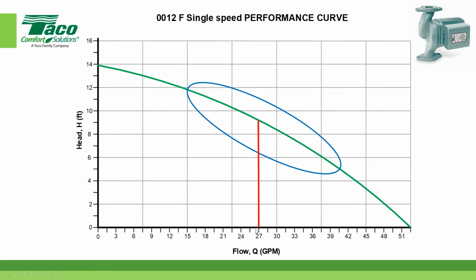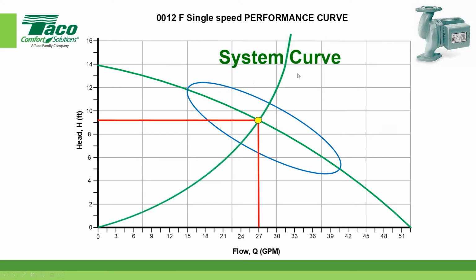The actual best efficiency point is right smack in the middle of that filet, or generally speaking, right in the middle of the circulator performance curve. So in this case, this would have the ability to do 27 gallons a minute at about 9 foot of head, and that would be its BEP, or best efficiency point. In this case, if that's where I was running, that would also be my operating point, and I could tell that if I knew what my system curve was. So that's what we're going to get into next. We talked about the circulator performance curve. Hopefully you feel good about that and have a better understanding of that. Now let's talk about what the system curve is, because you can see there's an interaction between the circulator performance curve and the system curve. And where they meet is where my operating point is going to be.